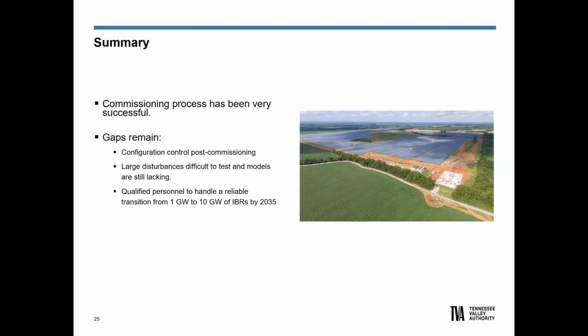The commissioning process has been going pretty successfully, especially that 14-day burn-in period where we require them to show good faith performance and do the testing up to that point and then have a good 14-day run. Some gaps that remain would be configuration control post-commissioning. Again, we have a good 14-day run, everything's fine, and then they go in and they tweak the PPC or they tweak something in the firmware in the controller, and things become difficult at that point to figure out what happened.